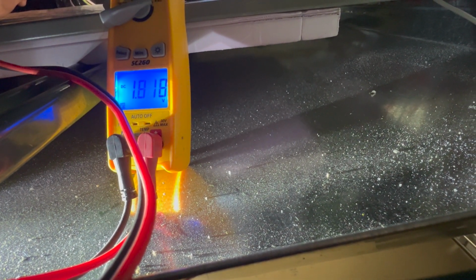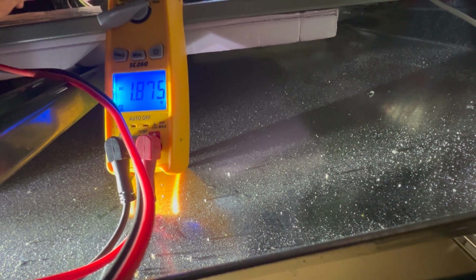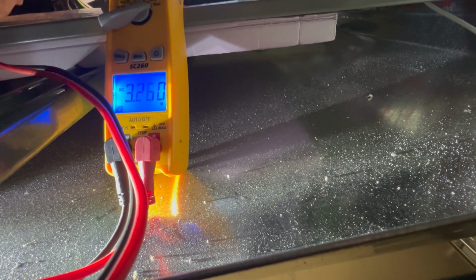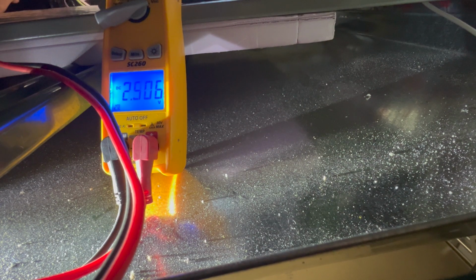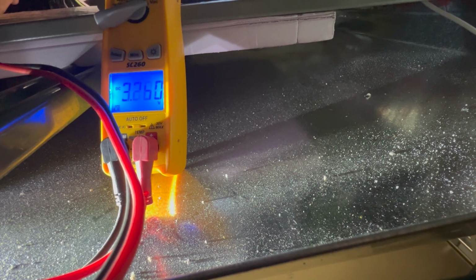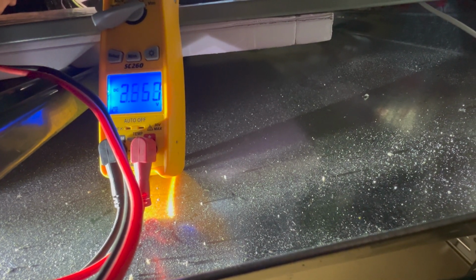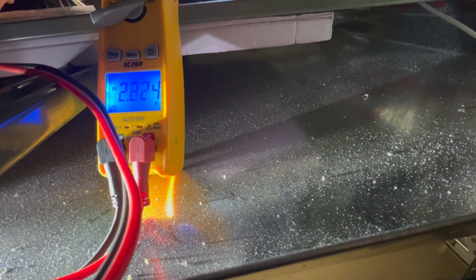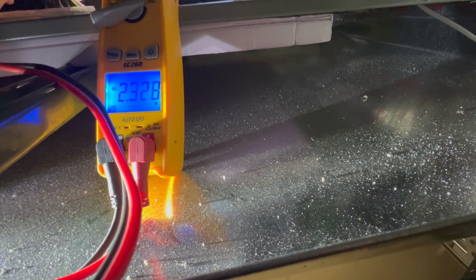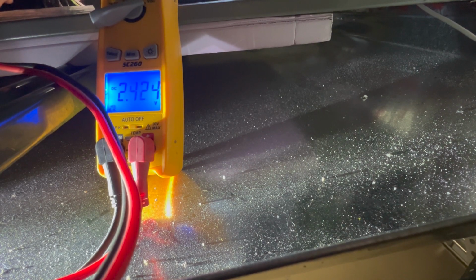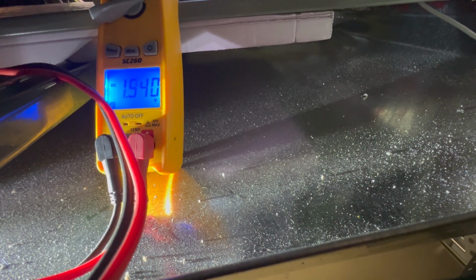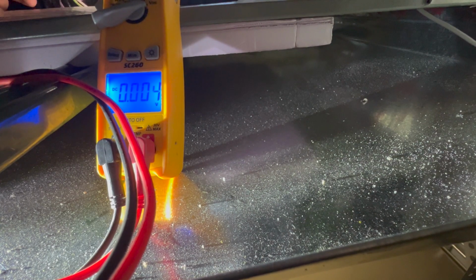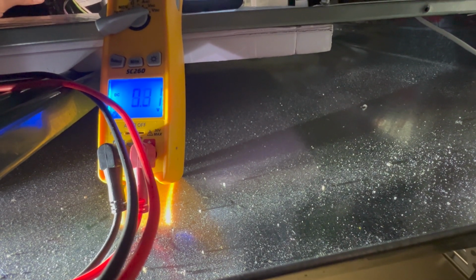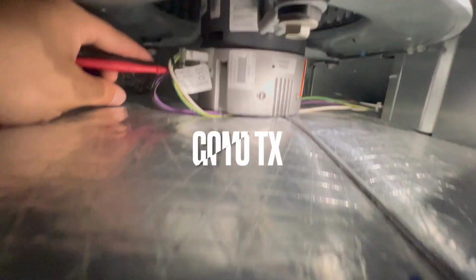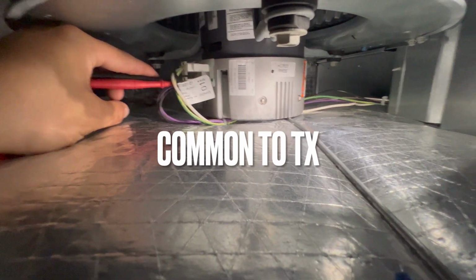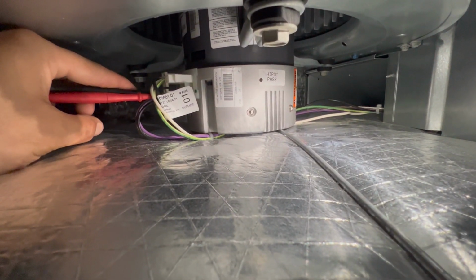So if you see it's changing, see how it's jumping up and down? That means the unit is communicating, is sending signals, meaning they call it pulse. So that's good. That means the board is communicating and sending signal to the blower motor. Now we're gonna check, in this case, from black to brown. This type of unit is Lennox, but pretty much it's the same.